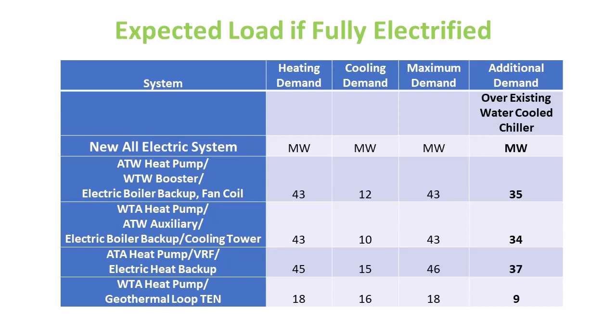The top three are some kind of air source systems. The one at the top is an air-to-water heat pump. Then we've got a water-to-air heat pump distributed, but with an air-to-water auxiliary. Instead of using gas boilers, we use an air source heat pump. But in northern climates, that's not going to work when it gets cold, so we go to an electric boiler, or just a straight air-to-air heat pump.